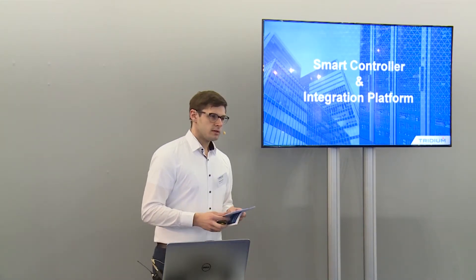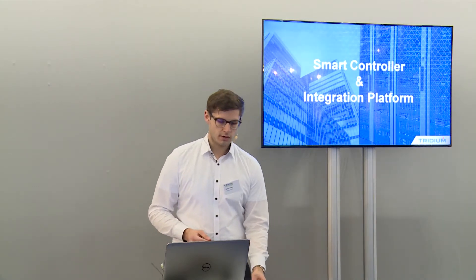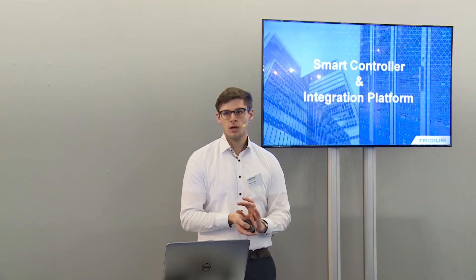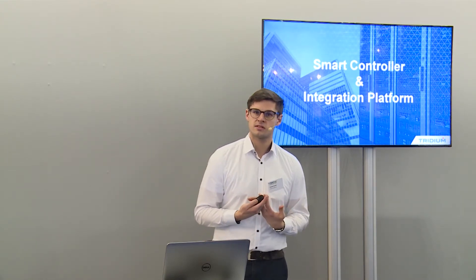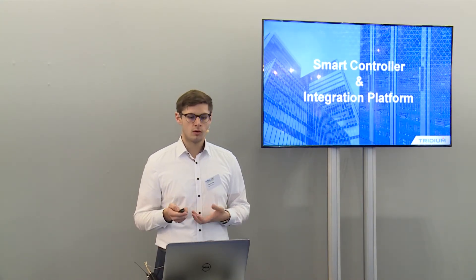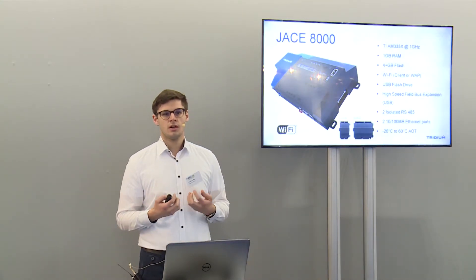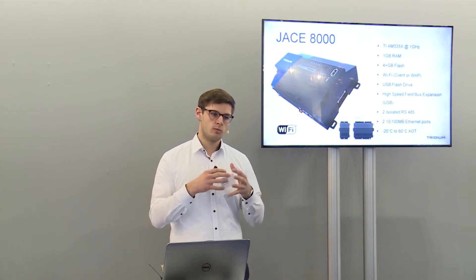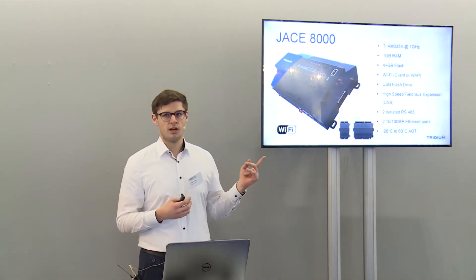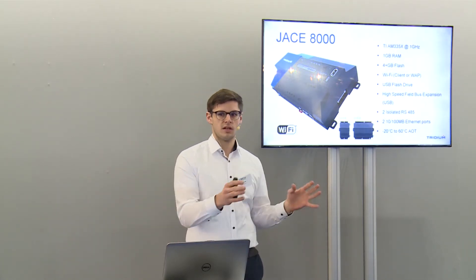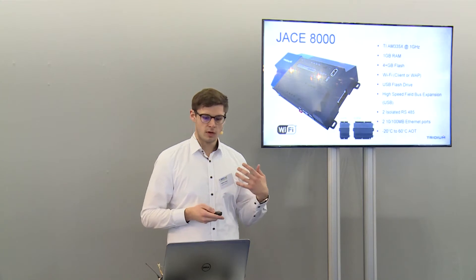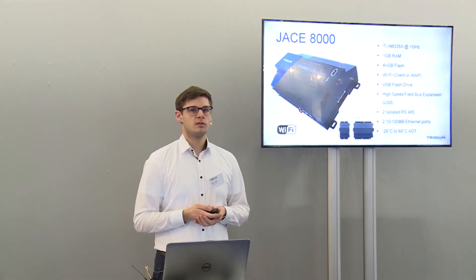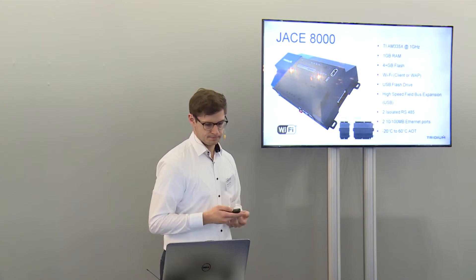We've talked about the scalability of the Niagara network. You can put the Niagara software onto your own device, but not every customer has hardware development capability, so we also provide a smart controller solution — the JACE 8000 — as a smart controller and integration platform. Whatever Niagara station runs on a PC can also run on the JACE, bringing Niagara very close to edge devices. With RS-485 ports and optional I/O ports, you can eliminate a lot of additional hardware in your building.